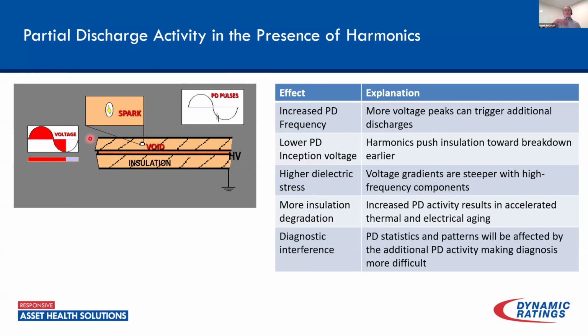Now, what happens as we introduce harmonics? We're going to start to see increased partial discharge activity. We're going to have more voltage peaks, which can trigger additional discharges. We're also going to see changes in the inception voltage. It's going to start occurring earlier and ending later, so the duration of the partial discharge event is going to increase. When we look at the transients, because the voltage gradient is steeper, it's also going to result in higher dielectric stress. There's going to be more energy because there's more pressure behind it, which is going to increase the insulation aging. So in the end, all of this is going to increase the level of insulation degradation that we're seeing.